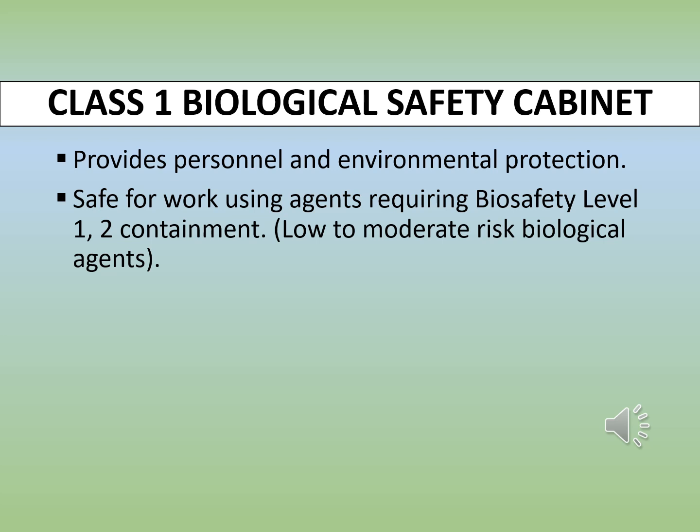Class 1 Biosafety Cabinet provides personnel and environmental protection. It doesn't provide product protection, and it will be more clear in the next slide. It's safe for work using agents requiring biosafety level 1 or 2 containment, means low to moderate risk biological agents that may cause minimal or potential hazard to the user and the environment.